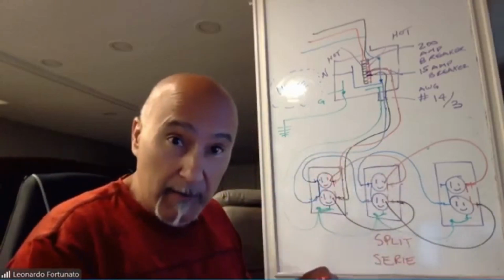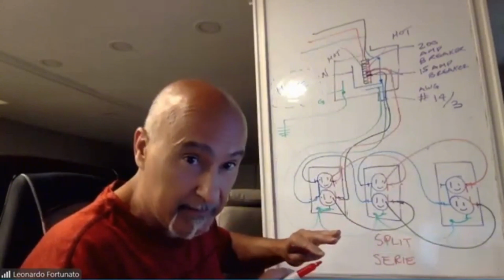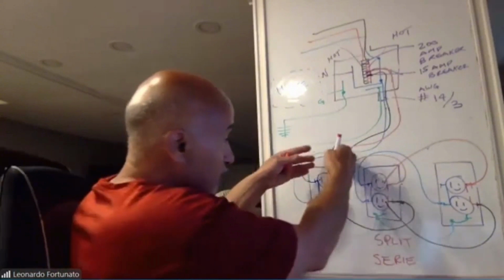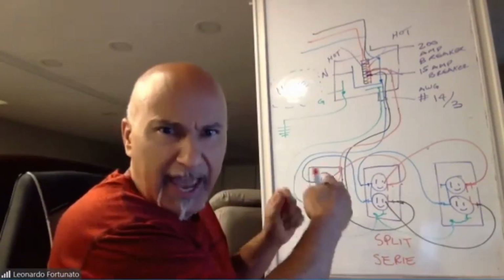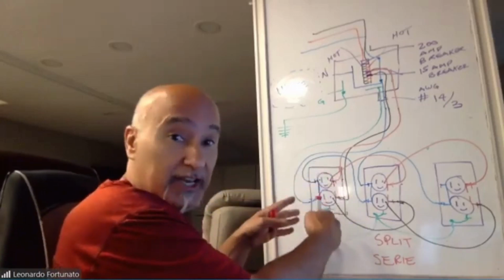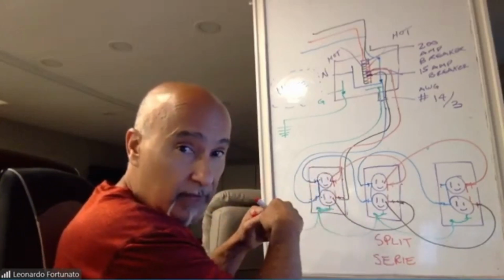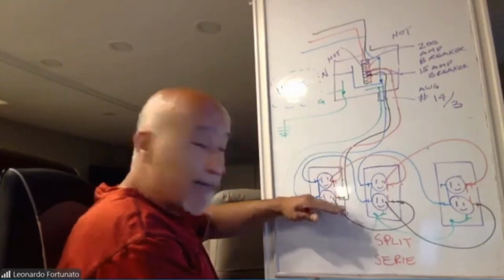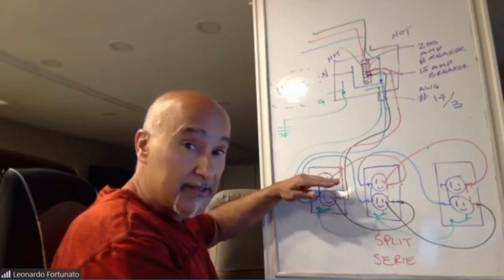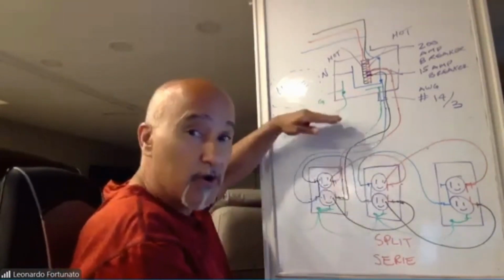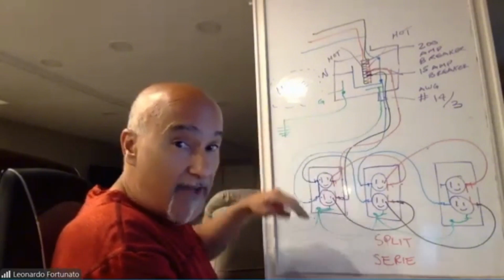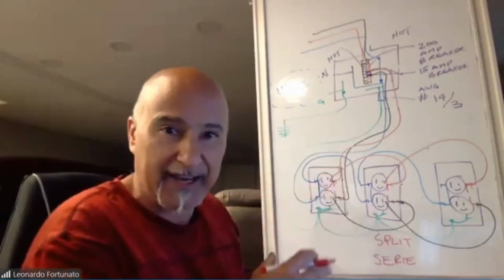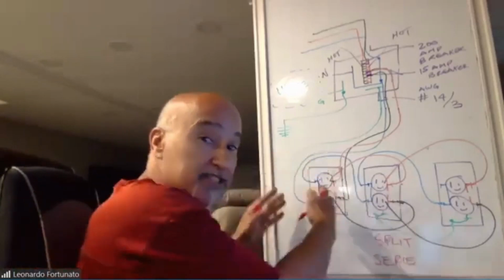Now, because we have a split circuit, this is one receptacle. If this was not split, it would have the capability of the maximum wattage. I can use up to total capacity 1800, safety capacity 1440. Agreed? But when I split this, the bottom is capable of 1440 safety capacity, and the top is also capable of 1440.